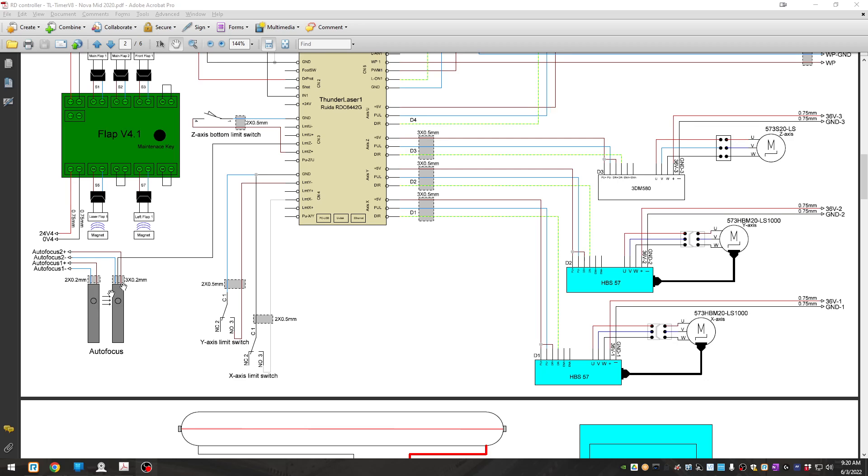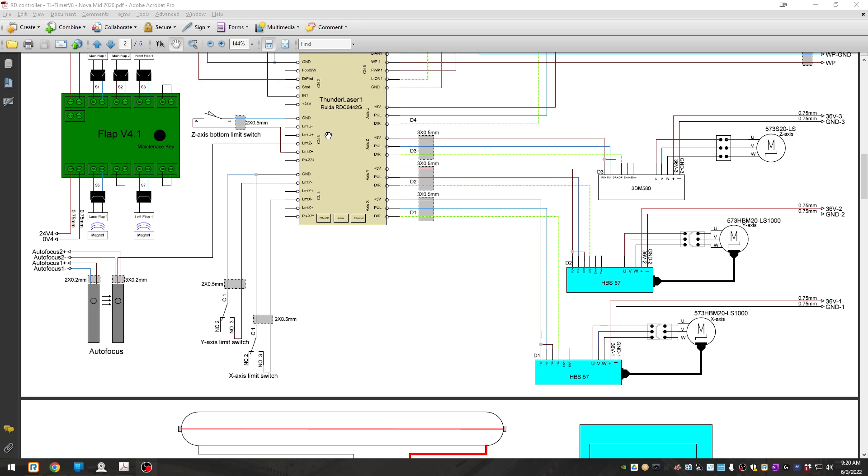So whenever this beam is broken, this goes low. It goes to ground. So by taking off that connection on CN3 and removing it and jumping that to ground, you should be able to see on your LEDs and on your control panel in the diagnostics that this toggles correctly to make sure that that's working right in the controller.